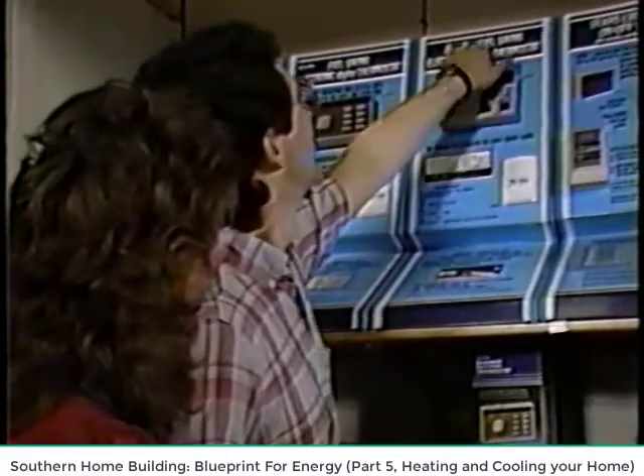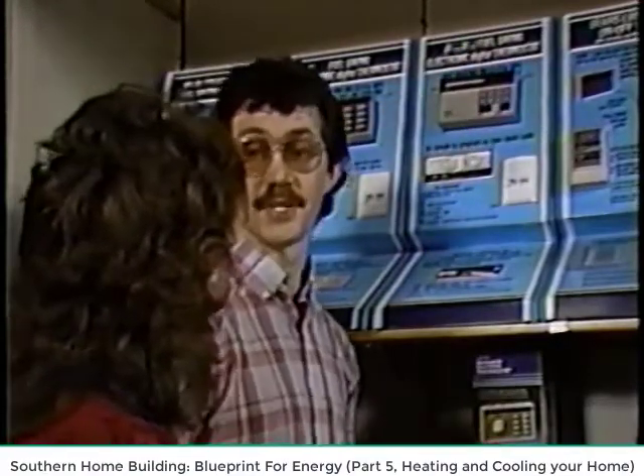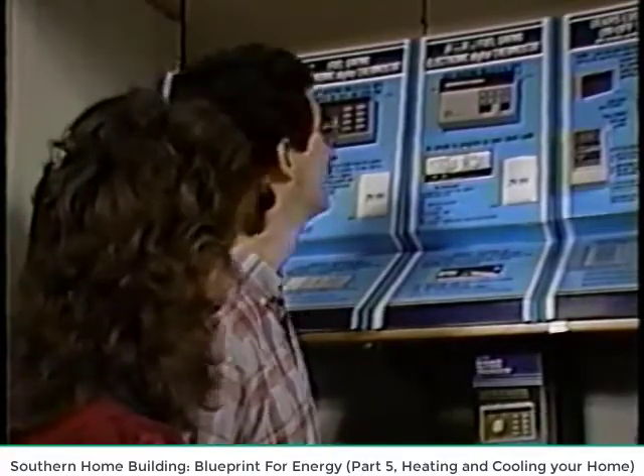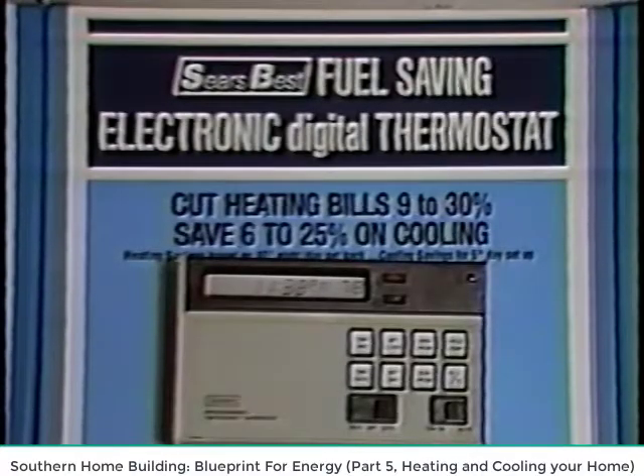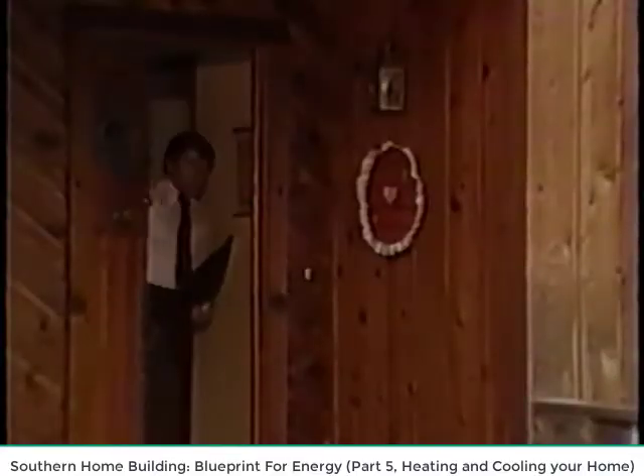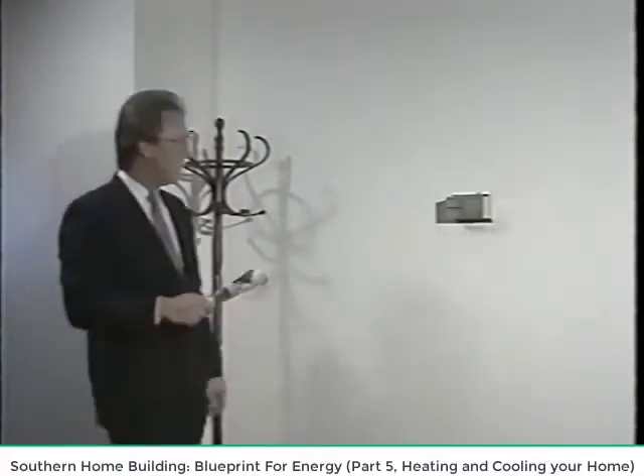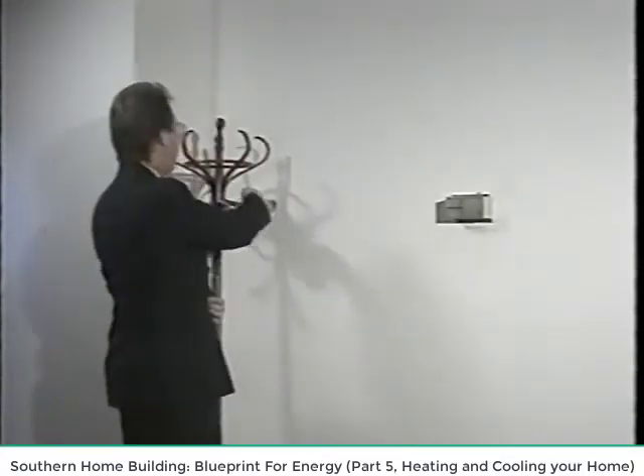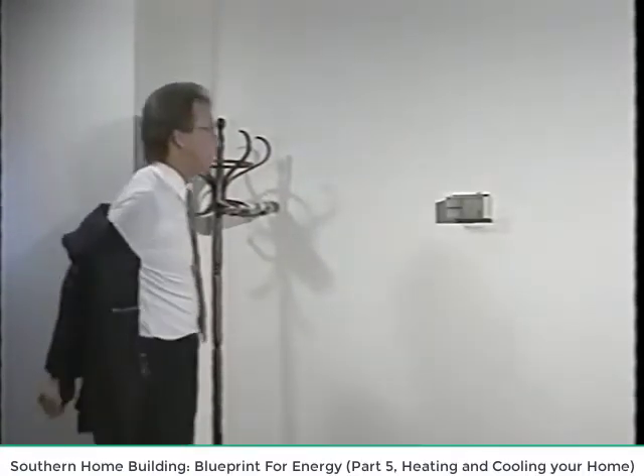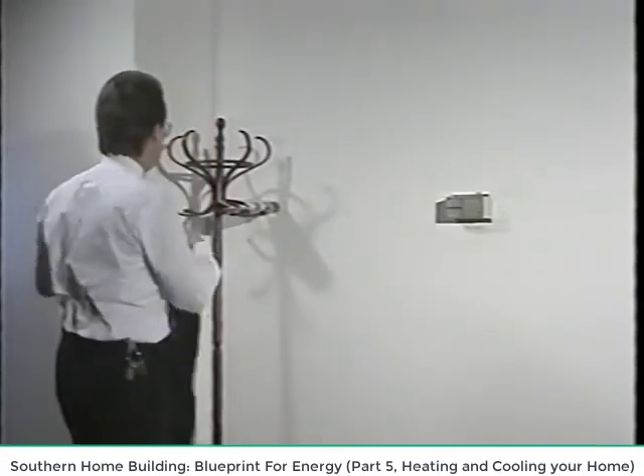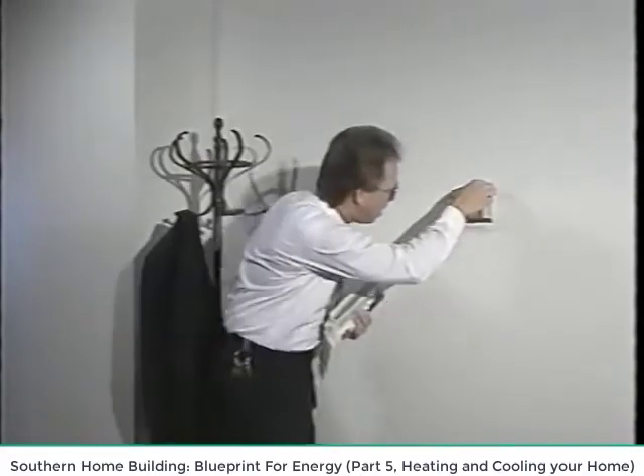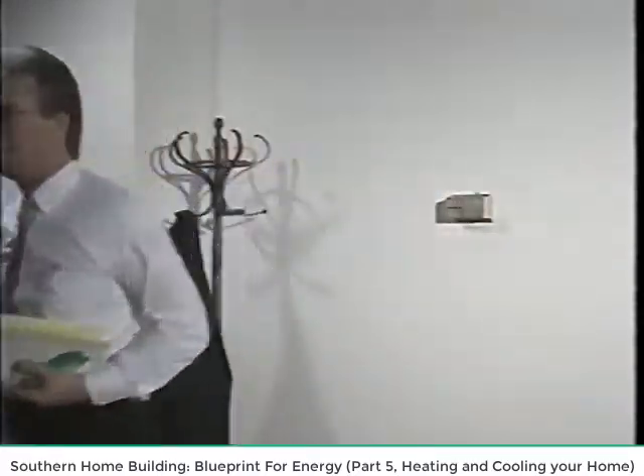The second type of energy-saving thermostat is the setback or programmable thermostat. Controlled by a computer chip, it saves energy by following a homeowner's instructions to operate the heat pump at a less comfortable temperature while people are away from home. Programmable thermostats provide convenience by bringing the house to a comfortable temperature at a pre-selected time. However, the same savings can be obtained by manually readjusting a regular thermostat, but the homeowner must return to the home, readjust the thermostat, then wait until the temperature reaches a comfortable level.